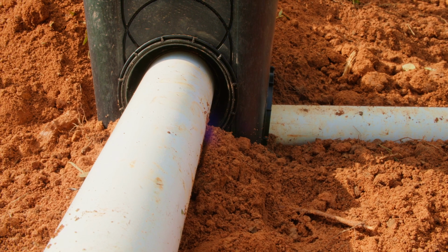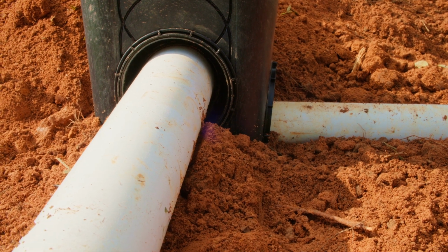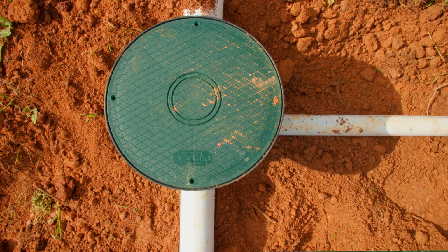This high hole will be for the inlet pipe. The inlet pipe will be at least a 3-inch Schedule 40 PVC. The outlet to the first trench will be the lowest hole. You will use 2-inch Schedule 40 PVC to plumb to that. When you are piping your intermediate hole, which will travel from one drop box down line to the next line, you will use 3-inch Schedule 40 PVC.